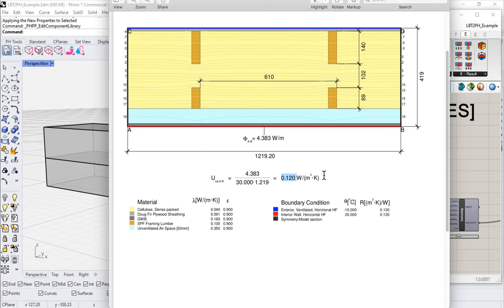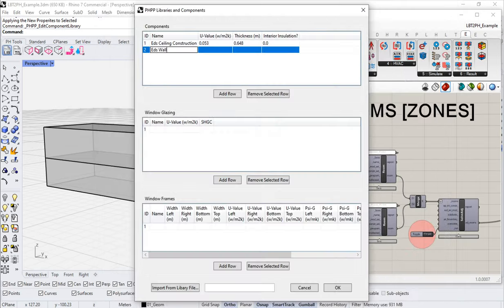We could also go to something like ASHRAE 90.1 Appendix A or ISO 6946 and get a value from a table. There are lots of different places you can get U-values from. In any event, we've got a total thickness of 419 millimeters and a total U-value of 0.12.